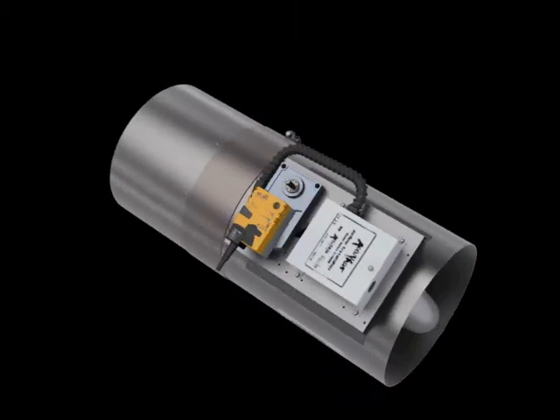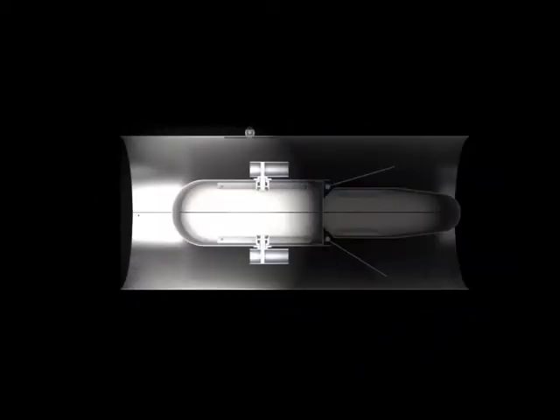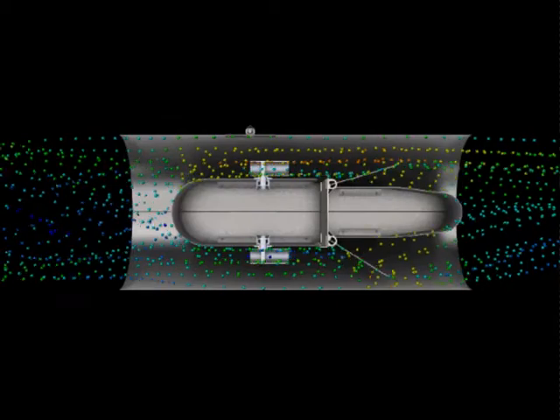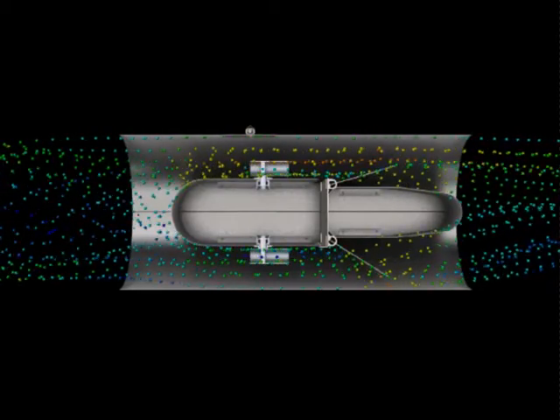Viewing the AccuValve from the inlet side, you'll see an airfoil-shaped compression section, which divides the airflow into two equal chambers. This causes air to accelerate and compress into laminar airflow, enabling enhanced turndown and installation options.